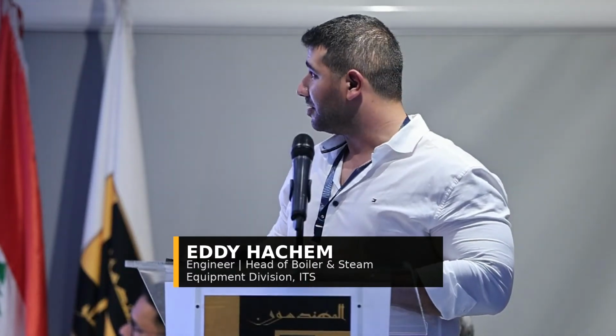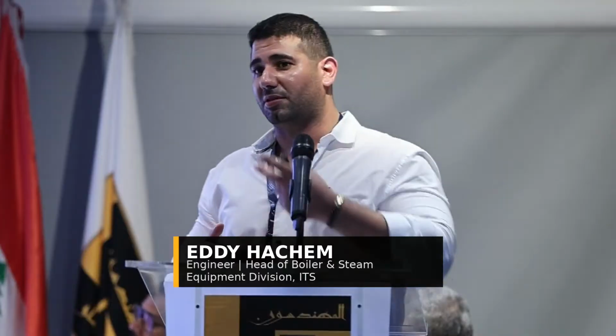Now let's move to clean steam. What you need for clean steam is two things: industrial steam and purified water. Purified water is different than WFI, water for injection, used in pharma. Purified water is simply obtained through a softener, sand filter, reverse osmosis, UV, and deionizers, and you get purified water. Then you pass it through a clean steam generator and you get clean steam.